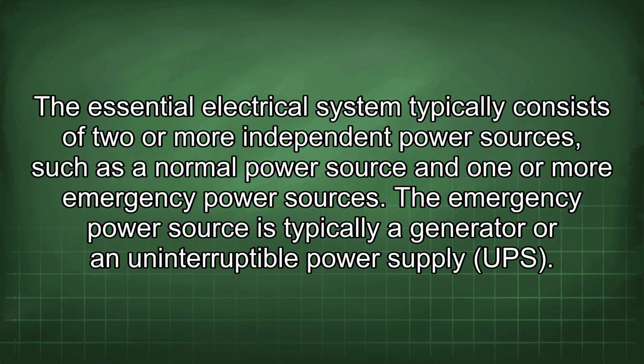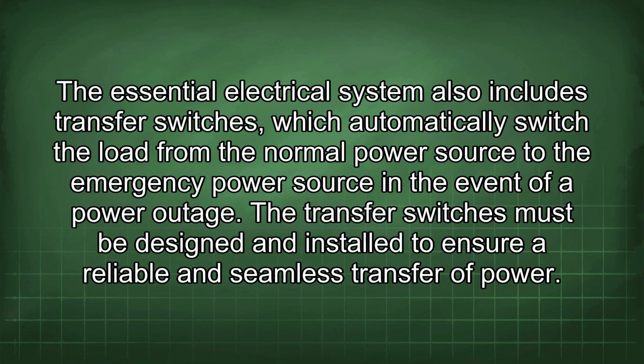The essential electrical system typically consists of two or more independent power sources, such as a normal power source and one or more emergency power sources. The emergency power source is typically a generator or an uninterruptible power supply (UPS). The essential electrical system also includes transfer switches, which automatically switch the load from the normal power source to the emergency power source in the event of a power outage. The transfer switches must be designed and installed to ensure a reliable and seamless transfer of power.